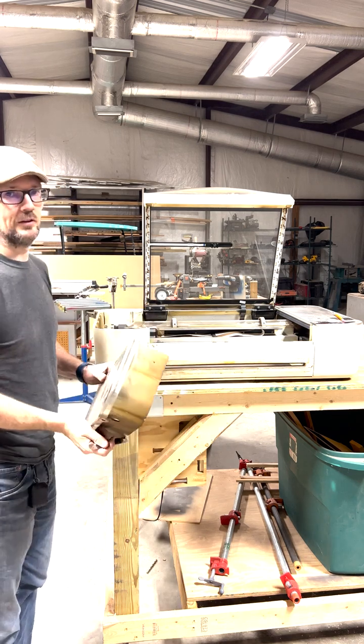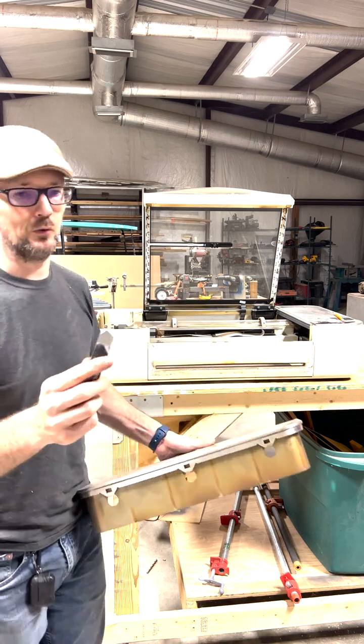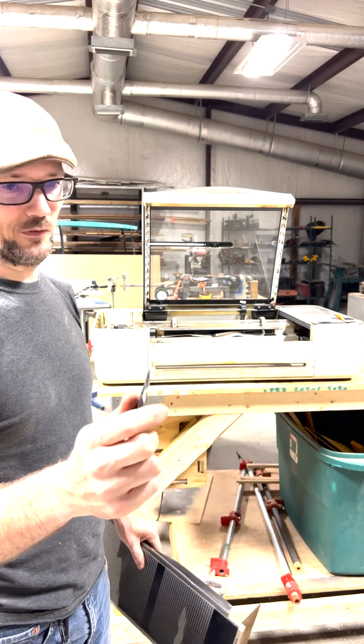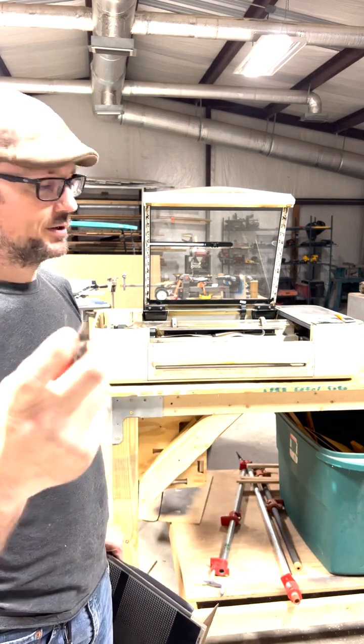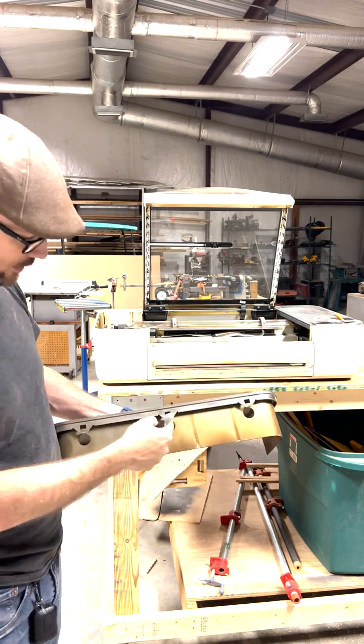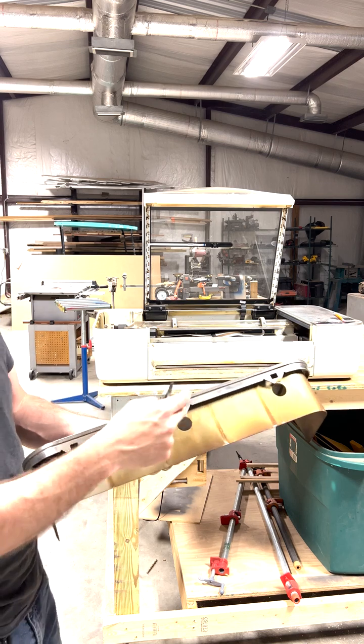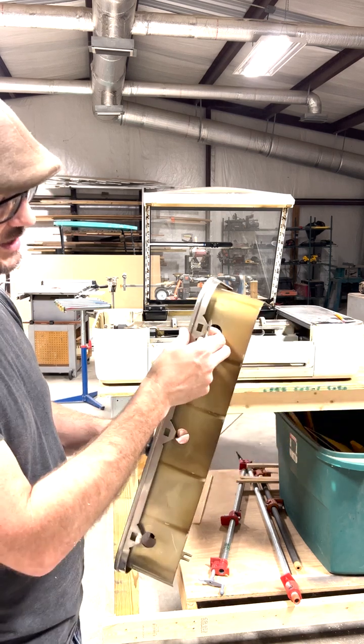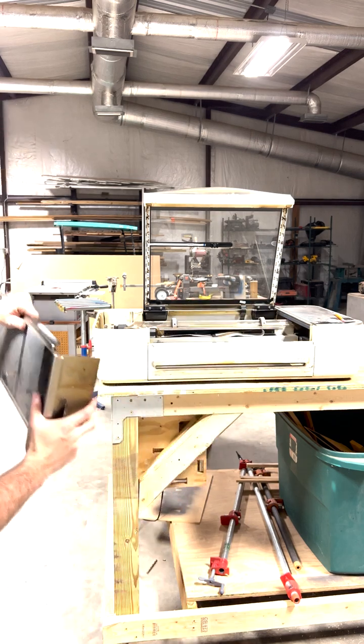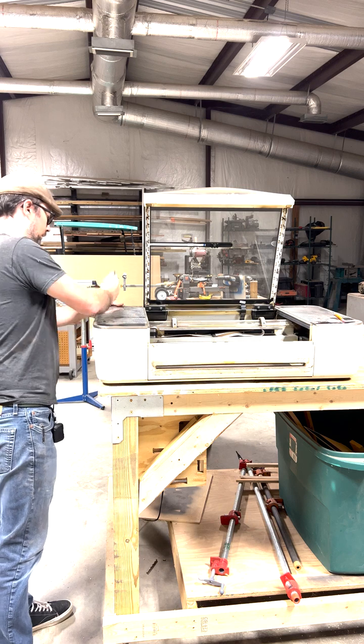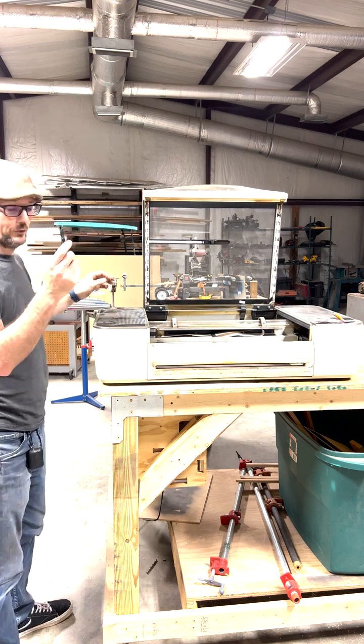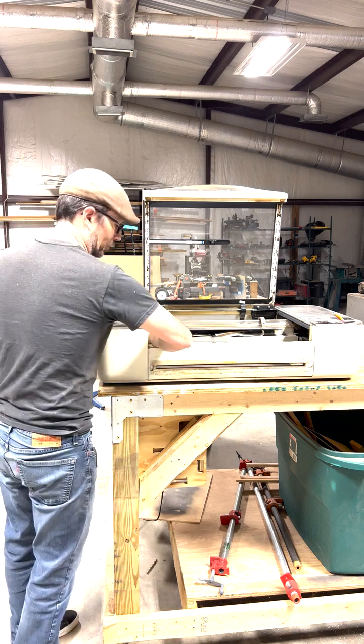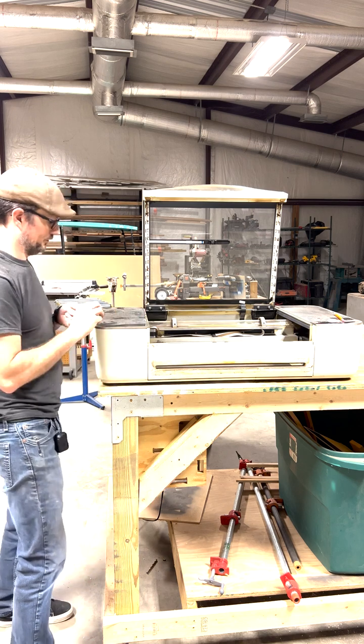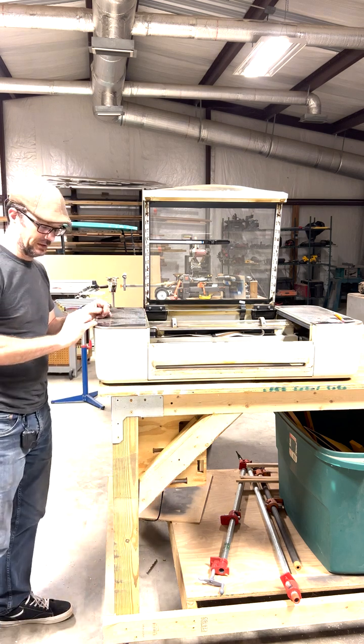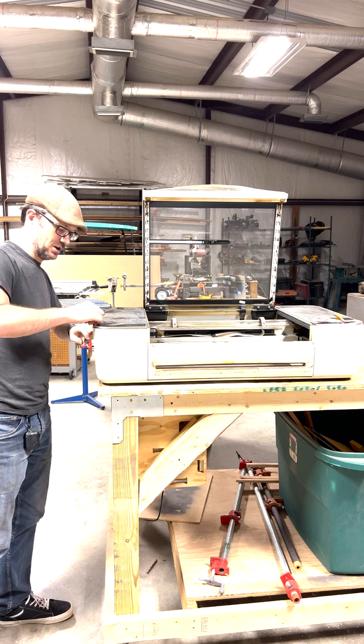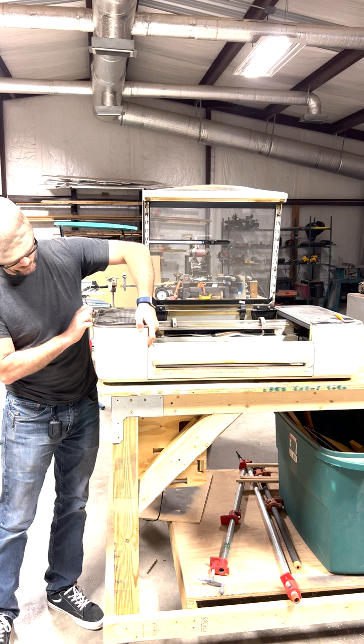Now, I have learned a trick to get these off that actually is pretty easy. You just need a pry tool, something along the lines of this right here. Something flat, strong, and a little flexible. So to get it off, you see these clips right here are what hold on the side of the lid to the machine. Now the side of the lid, the machine is pretty flexible, and what I have learned to do is with this installed, all the way, lid up, you get your pry tool, and you can put your finger in there and you can feel where the tinfoil tape is. You don't actually have to remove the tinfoil tape. What you'll do is you get your pry tool and you push it in next to the lid and the frame of the machine, the plastic. You push in and you just wiggle up on it a little bit while you push down on it.